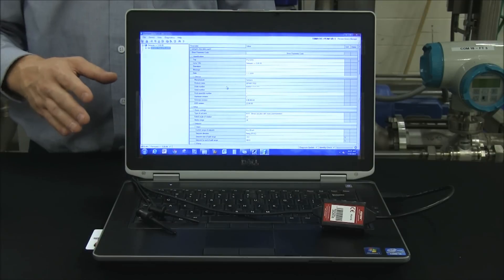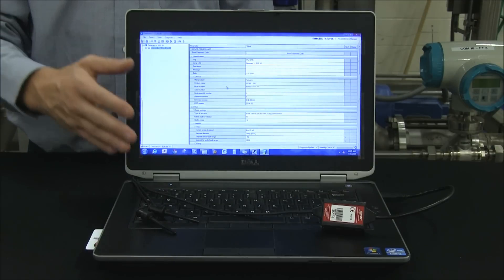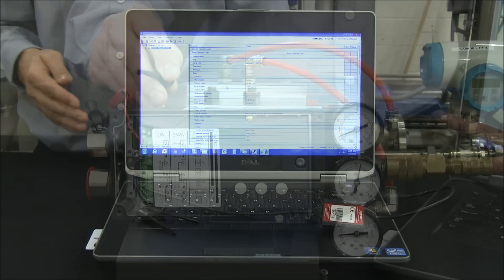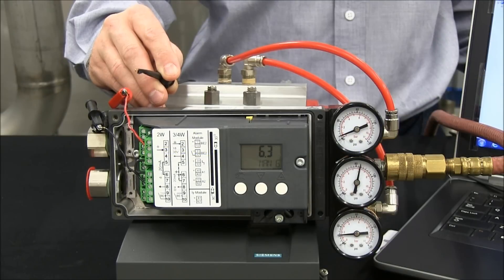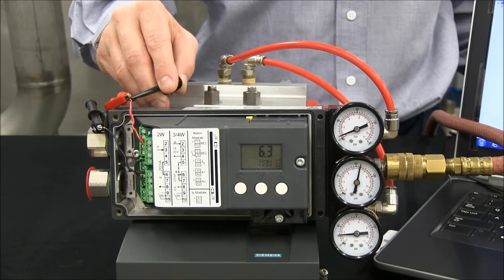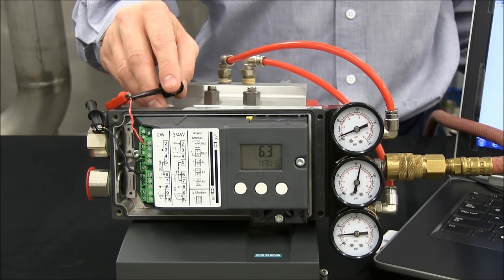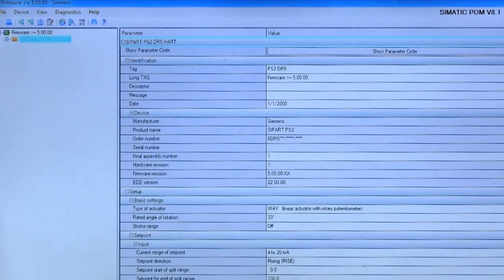Here we have a computer with PDM software installed and a HART modem. To connect to our PS2, all we need to do is clip the HART leads to the PS2 signal current loop. Once connected, launch Simatic PDM software and navigate to the valve performance test wizard.